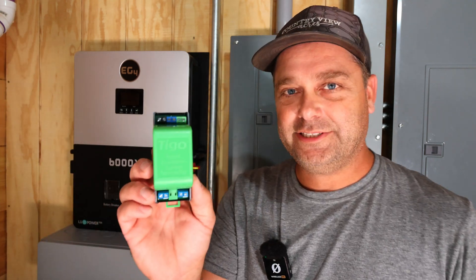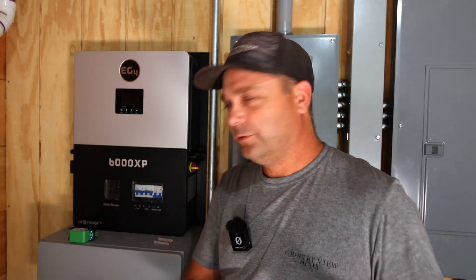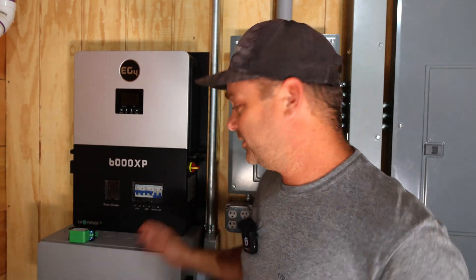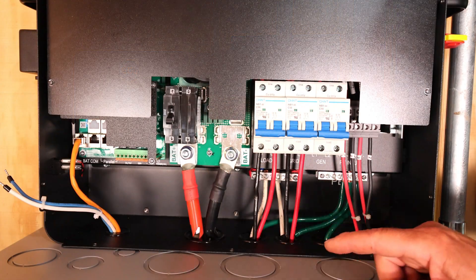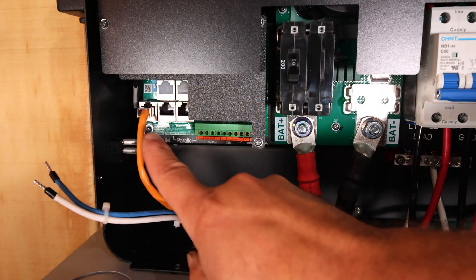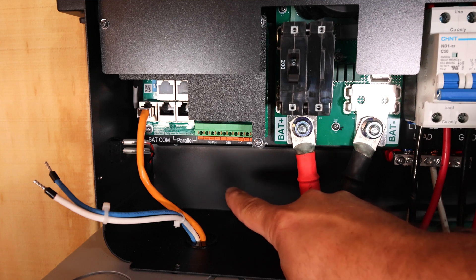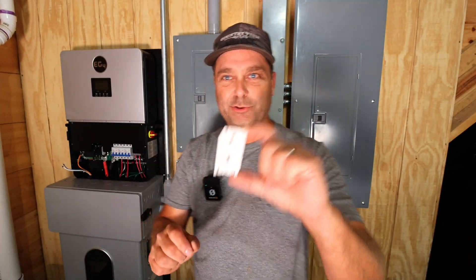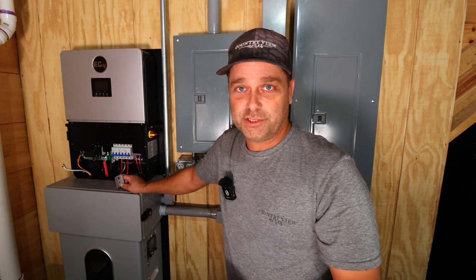I'm going to install the Tigo rapid shutdown transmitter inside of the 6000 XP, wire it to the signal core, and mount it inside the inverter as well. Looking inside the 6000 XP on the communication side, there's a big void behind the connections, and that's where we're going to put the Tigo shutdown transmitter. The transmitter mounts to a piece of din rail — I cut this one about two and a quarter inches long — and we'll mount it to the back of the inverter using some self-tapping screws.